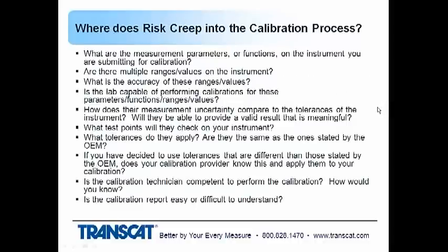Now let's talk a little bit about the calibration process and where things can go wrong there. What are the measurement parameters, the functions, ranges of the instrument you're submitting for calibration? Does it have multiple ranges, multiple readings, or is it a single-use instrument? Then you have to get into the accuracy of those ranges or values or of the instrument to determine what you think the tolerances should be for acceptance. This is what you or someone in your organization should have based a decision on when you selected it for the suitability for intended purpose category. You base that likely on what the manufacturer stated it will meet. Sometimes you'll change that to what your tolerances are required to meet for your production process.